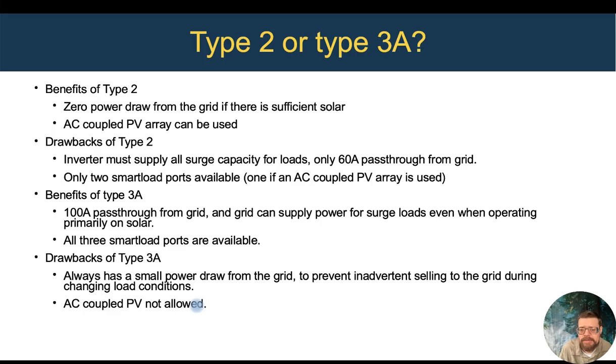Now, the flip side of that is that if you have a lot of really big loads, operating in parallel with the grid is really providing the surge for those big loads, and the inverter doesn't have to do that. If you're doing a Type 2, when you're operating from solar, the inverter is completely responsible for running that load, and because the grid is coming in on the 60 amp smart load, you've only got 60 amps pass through coming in from the grid rather than 100 amps when you're coming into the AC in. So if you're doing a system where your loads are smaller and you can really operate fully off-grid most of the time and only occasionally use the grid, Type 2 might make more sense.